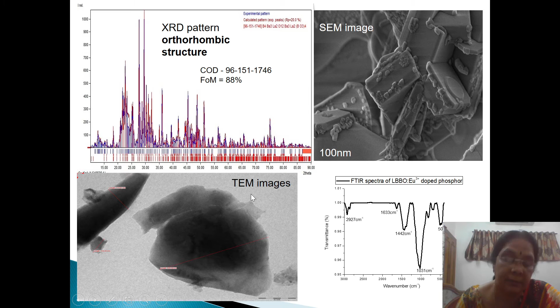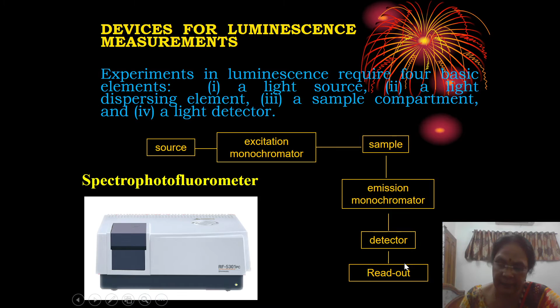Devices for luminescence measurements. An experiment in luminescence requires four basic elements, that is light source, light dispersing element, a sample compartment and a light detector. This is a photofluorometer. Here we have the source and excitation monochromator. All these are in this compact box. There is a sample holder where you can put your samples. Then it is the emission monochromator. This one is excitation, this one is emission, then the detector, and you can read the results.